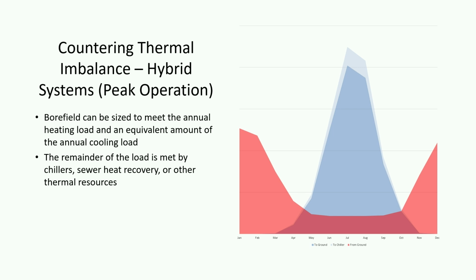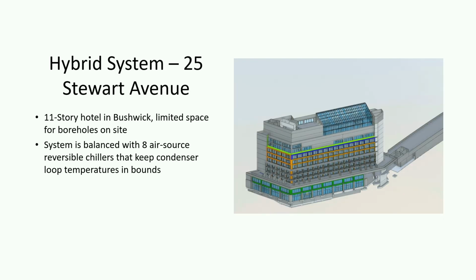So what you'll have is, as your condenser water temperatures rise and your geothermal system is not able to keep up, some type of chiller or other thermal resource will come online and knock those temperatures back down. That will serve to balance your system over the course of the year, and it's fairly simple to install.